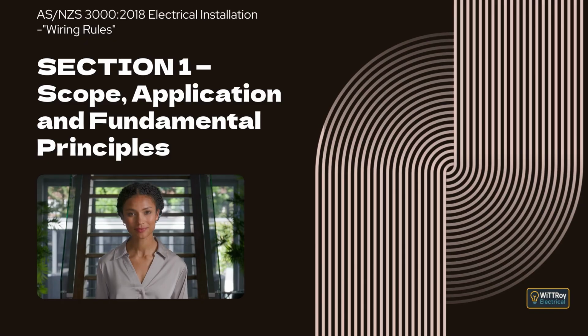The standard also gives maximum disconnection times. For example, some circuits must disconnect within 0.4 seconds, especially socket outlets and handheld equipment. Other circuits, like fixed equipment, are allowed up to 5 seconds. Sometimes extra bonding is needed if there is metalwork around the area, just to make sure the protective device can operate within the correct time.